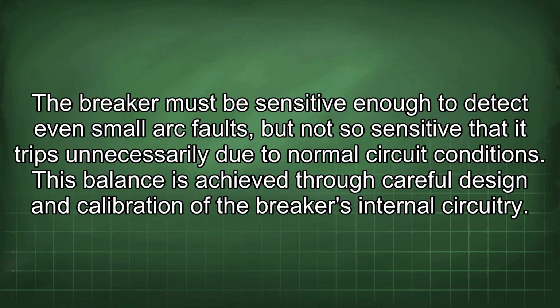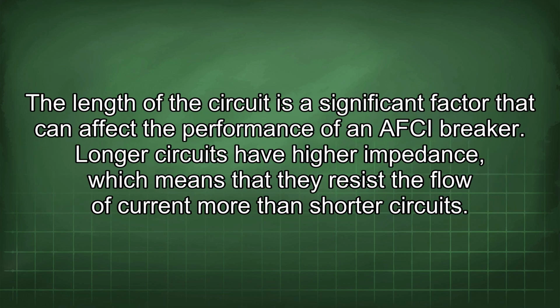A breaker must be sensitive enough to detect even small arc faults, but not so sensitive that it trips unnecessarily due to normal circuit conditions. This balance is achieved through careful design and calibration of the breaker's internal circuitry. The length of the circuit is a significant factor that can affect the performance of an AFCI breaker.